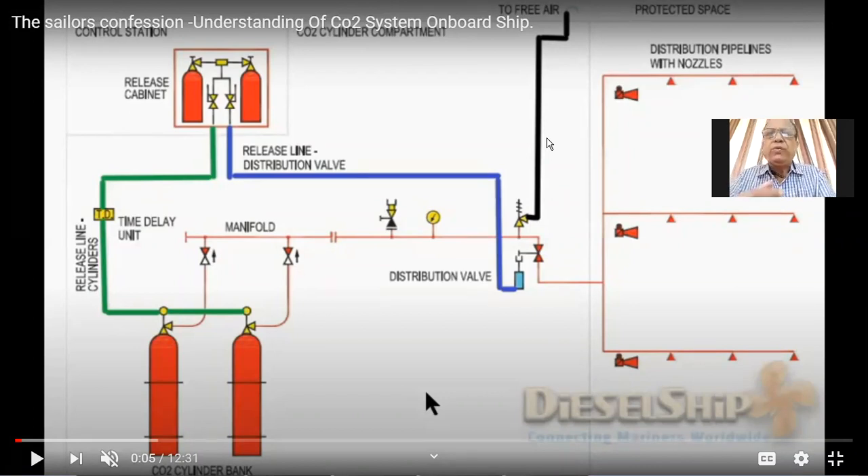When you open the cabinet door in case of fire, the first thing that happens is a very loud fire alarm — both visual and audible — is raised in the engine room. At the same time, all engine room blowers and ventilators are electrically shut off to isolate the air inlet to the engine, so that the fire does not propagate. That is the very first step.